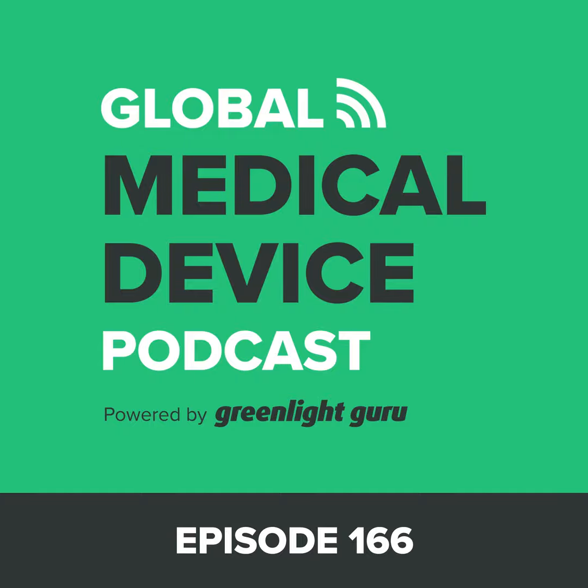I definitely agree with you, John. And I would just like to make one other point, and then I have some recommendations based on this guidance. To me, what I just said and what you just said, there's nothing new here. This has always been my approach. One of the problems that I have with the way that the 10993 standard is laid out, and as I said earlier, this is sort of the gold standard for biocompatibility, is they have these tables depending on whether this is a skin contact or an implant or whatever it is. And okay, if you're doing this kind of device, this is the kind of testing that you need to do. That kind of device, this is the kind of testing. I think that's okay as a starting point, but I never take that as gospel.